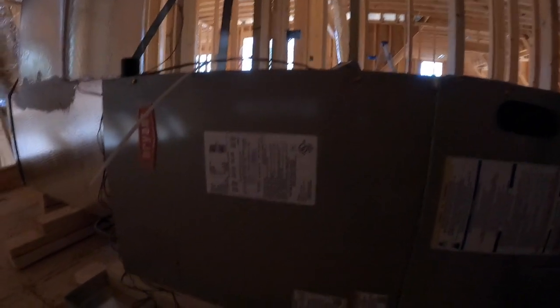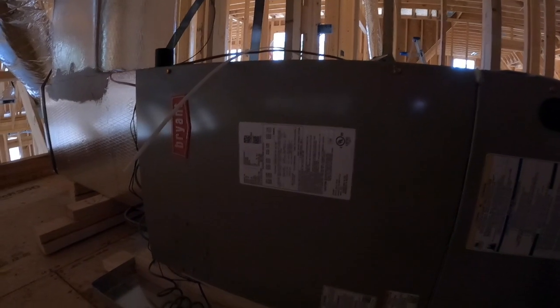There's a float in there, and if this pipe fills up with water because the drain is clogged, it floats, and the way we wire it up makes the thermostat go blank, so the homeowner knows immediately they have a problem. We also put a wet switch in the pan, so if this thing even gets moist, it turns the unit off, so they immediately know they have a problem.